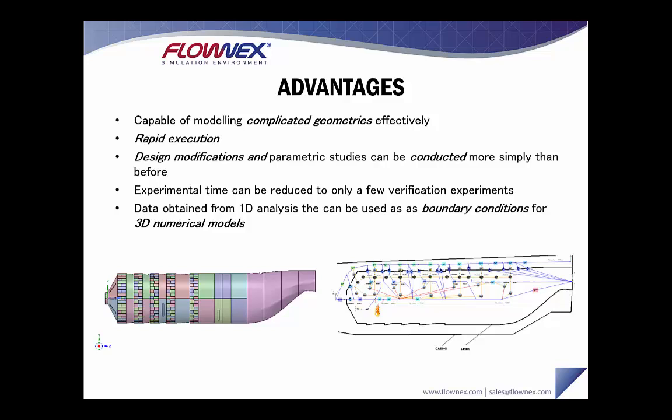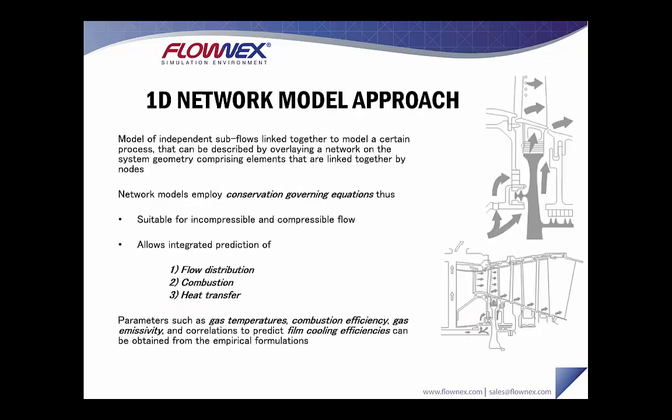Some of the advantages of a one-dimensional network model are that it's capable of modeling complicated geometries effectively. Its execution is rapid, typically only a couple of seconds for large models. Design modifications and parametric studies can be conducted more simply, and experimental time can be reduced to only a few verification experiments. Also very importantly, data obtained from this type of analysis can be used as boundary conditions for 3D numerical models. Network models like Flownex employ conservation and governing equations, suitable for incompressible and compressible flows, and allow the integrated prediction of flow distribution, combustion, and heat transfer.